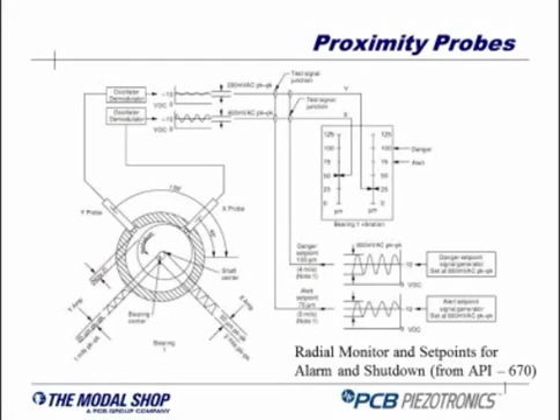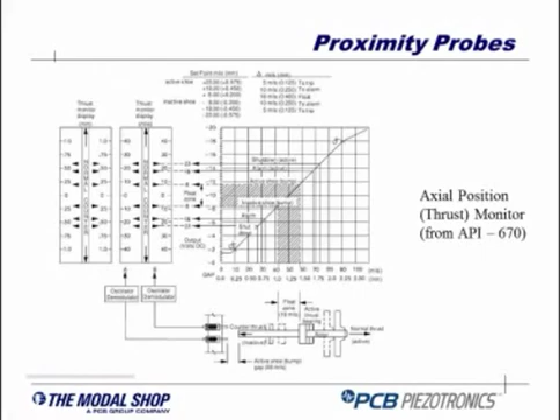If you look at what type of measurements are being taken, this is just an example there. You can measure the radial vibration, and for each prox probe you get a dynamic signal, and you can look at the RMS or peak level of that signal and translate that into an alert or a shutdown point. Same thing in the axial direction. Since those are turbines, you're going to find a lot of thrust and energy going not only in the radial but also in the axial direction.